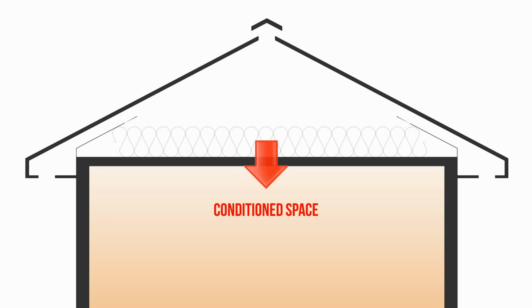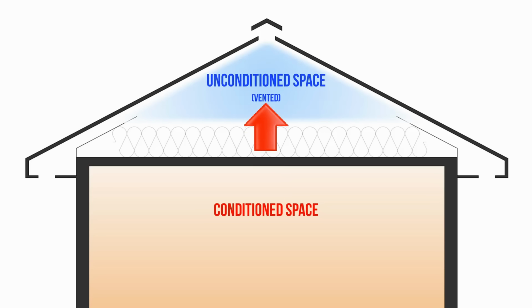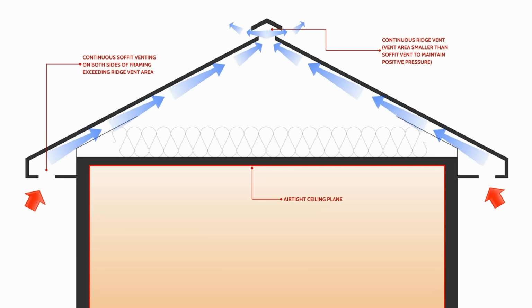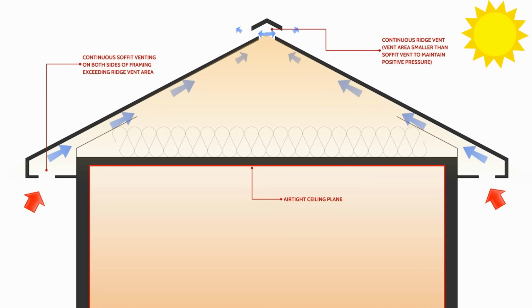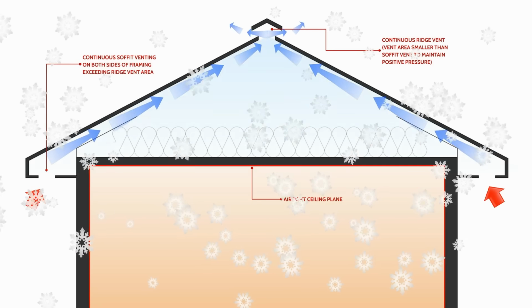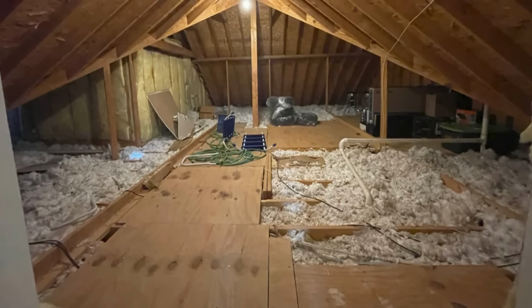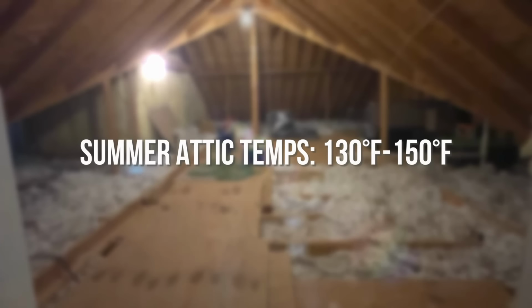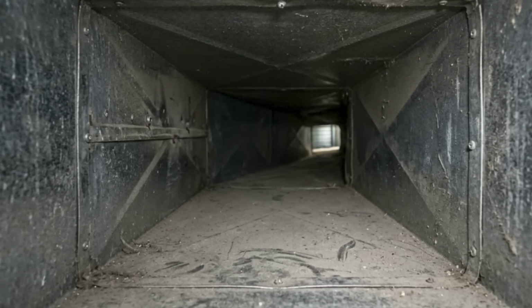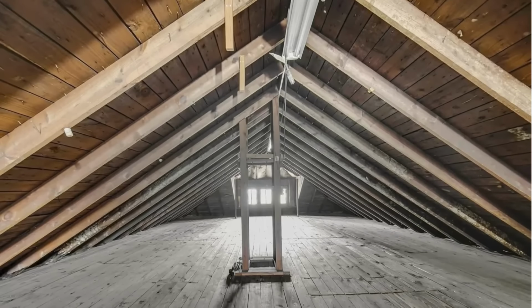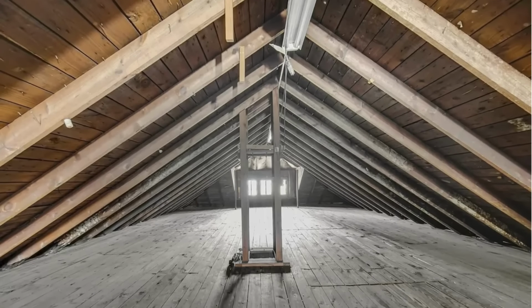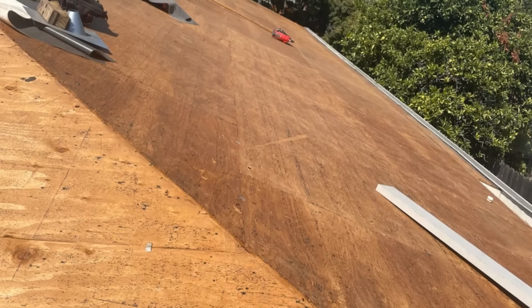By definition, a vented attic is designed to be outside of the thermal envelope and uncoupled from the air pressure boundary of your home. It's open to the outdoors through soffit and ridge vents, which means that in the summer it's incredibly hot, and in the winter it's freezing cold because, well, it's outside for all intents and purposes. Attic air temperatures on a typical summer afternoon easily reach 130 to 150 degrees. Think about that for a second. Inside your ducts, you have 55-degree conditioned air. Directly outside your ducts, in the attic, you have 130-degree or 150-degree air and a screaming hot roof deck.